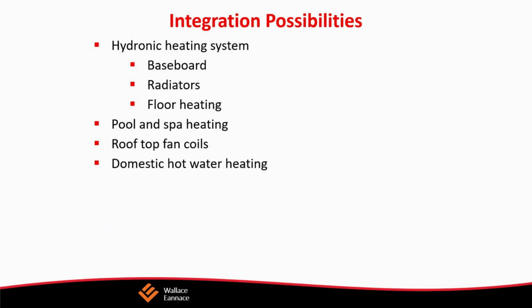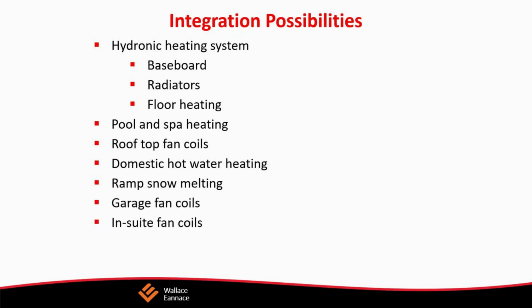We would probably really want to consider a lower temperature system design. The advantage of that is that the lower the water temperature, where we can still continue to heat the building, the more it allows a modern condensing boiler to operate in its condensing zone, which means that as long as the return water temperature is below 140 degrees, the boiler will condense, and it will be operating at very high levels of efficiency.